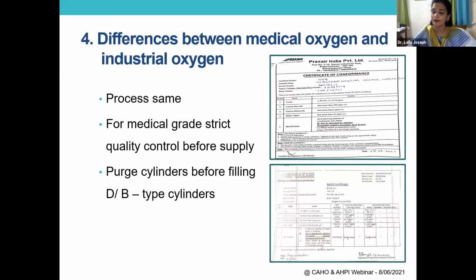Another thing with the manifold: with every filling of cylinders for medical grade oxygen, there's purging, meaning the inner surface of the cylinder is actually purged with oxygen before it is filled, which doesn't happen for industrial grade oxygen. Other than that, there aren't many differences.